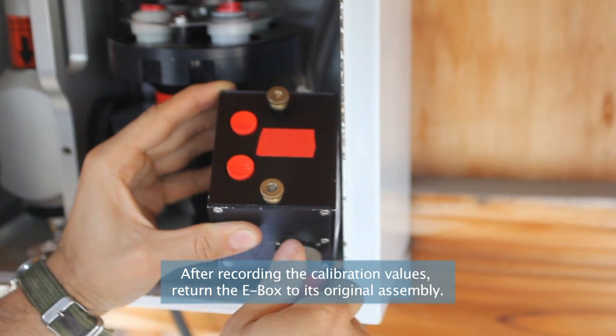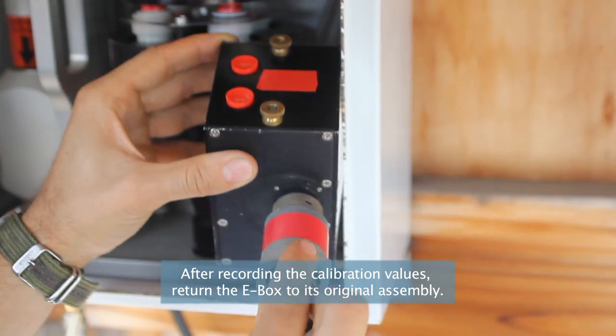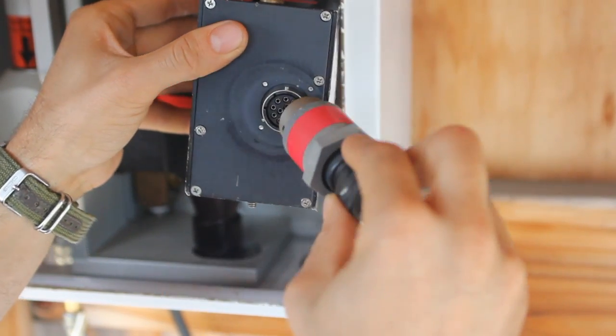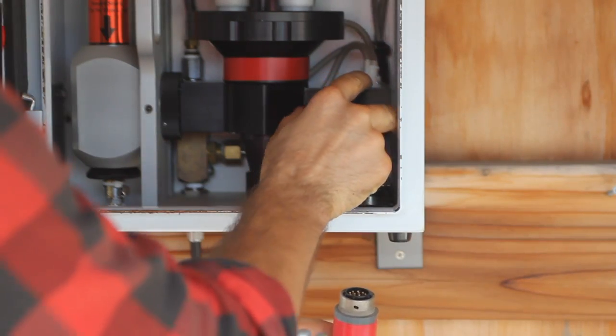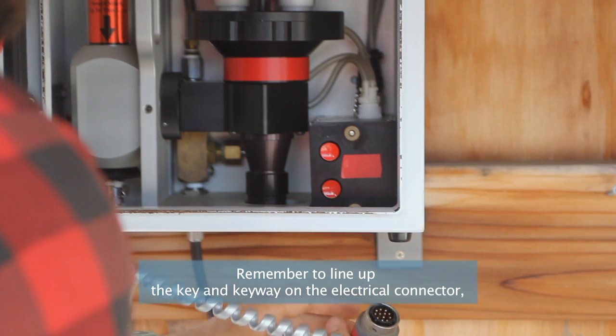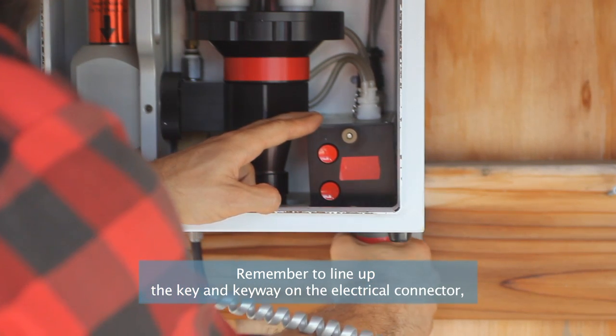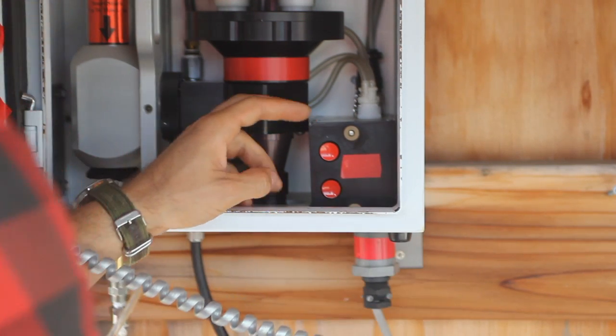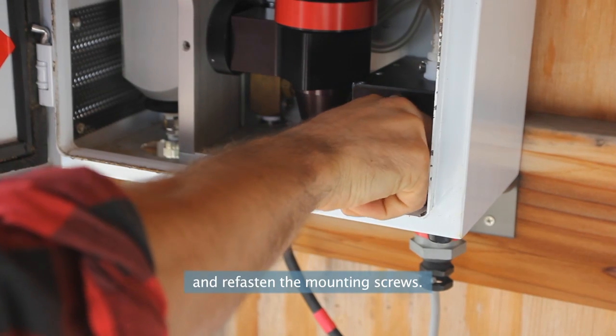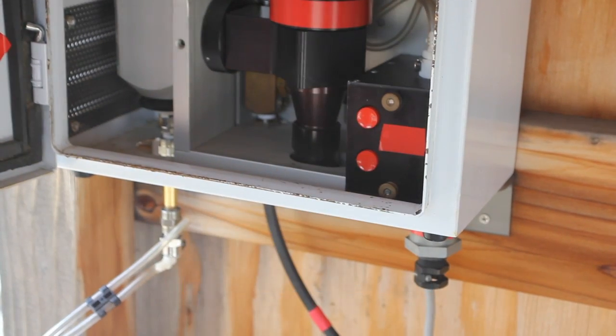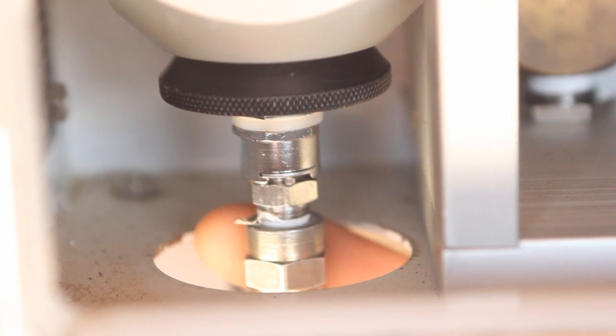After recording the calibration values, return the E-box to its original assembly. Remember to line up the key and keyway on the electrical connector, and refasten the mounting screws. Remove the probe and reinstall the plug and black plastic cap.